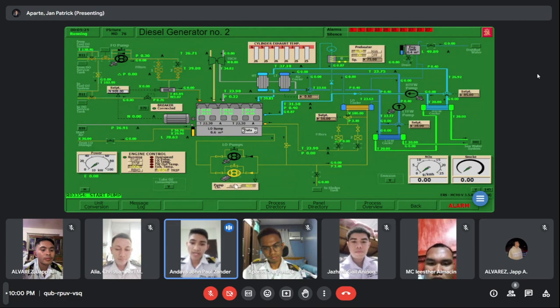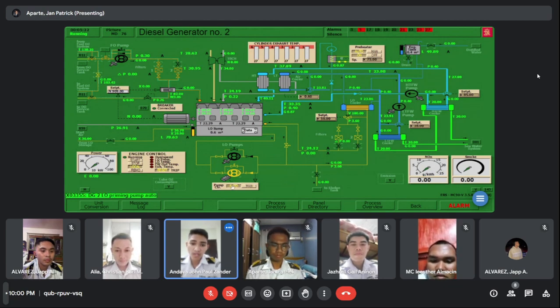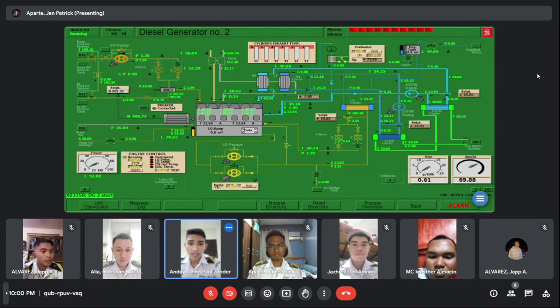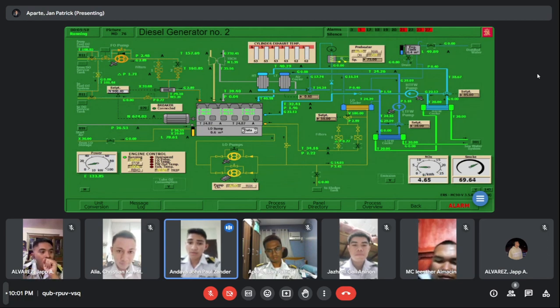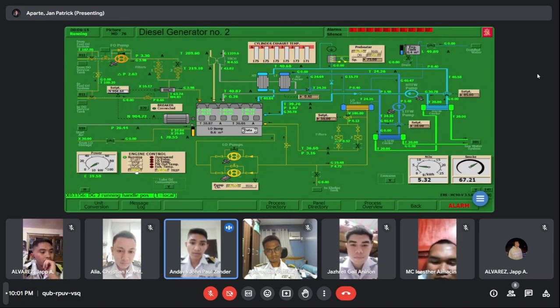After lining up the four systems and other systems that support our DG number 2, if all is ready, we are good to go for the test run of the generator of DG number 2. So start. It is already on local, so we can direct it to start. Okay, and then let's wait. That's the least we can do. We wait because there is an alarm coming from the fuel filters in the fuel oil system, so we need to rectify it. After the starting, once started, put DG number 2 on remote.